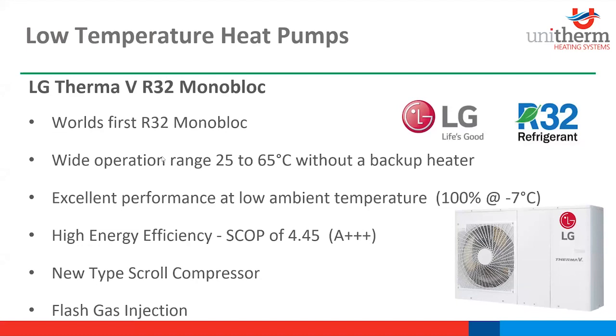Now that's basically unheard of, and I'll talk to you about that again. But a normal standard air to water heat pump will heat up to 52 to 55 degrees, and then it'll bring in the backup heater to heat it up to 60 for doing disinfection and stuff like that. So the LG Therma V can heat up to 65 degrees without a backup heater. Excellent performance at low temperatures: 100% performance down to -7.